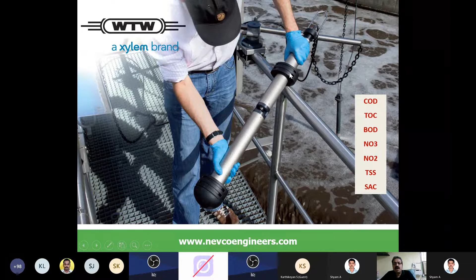So this is an advanced optical design, optical measurement, highly accurate, high repeatability, high long-term stability, automatic drift compensation, no regular zeroing or calibration required, waterproof, maintained UV-visible spectrophotometer, from 200 to 720 nanometers. As I say, this is the measurement window. This window will dip in the water. Then you can find out how much is your COD, how much is the BOD, how much is the TOC, how much is the TSS. So everything you can see.